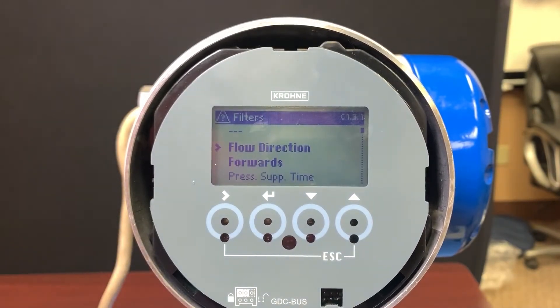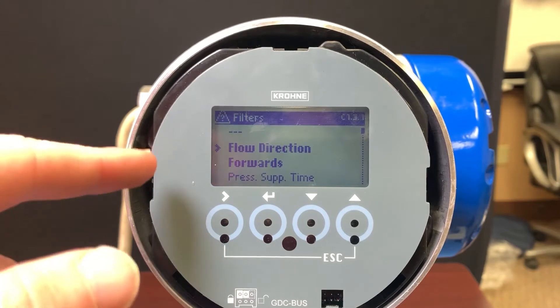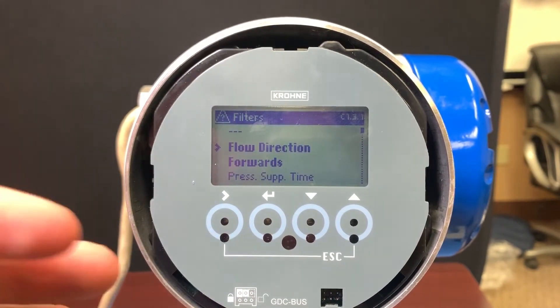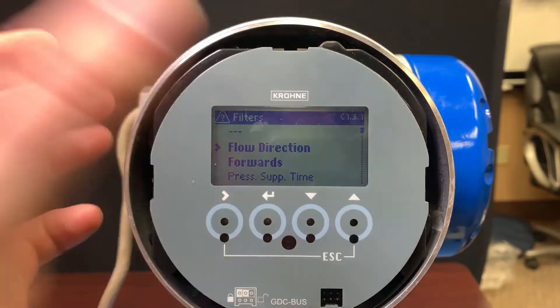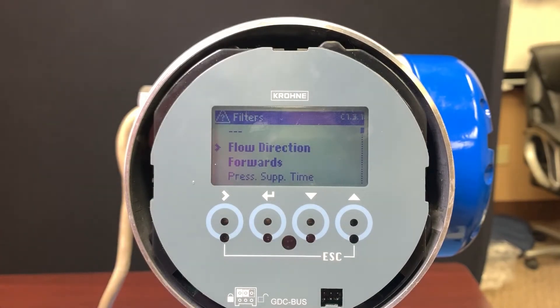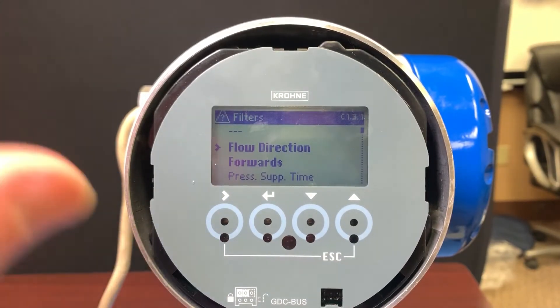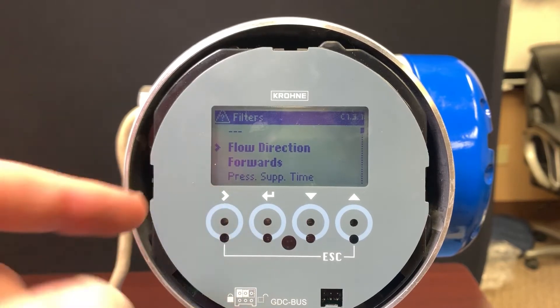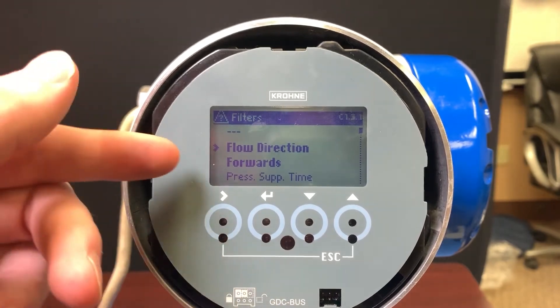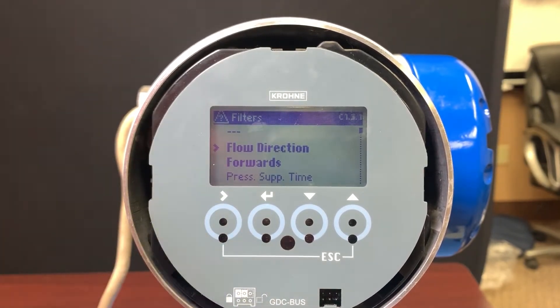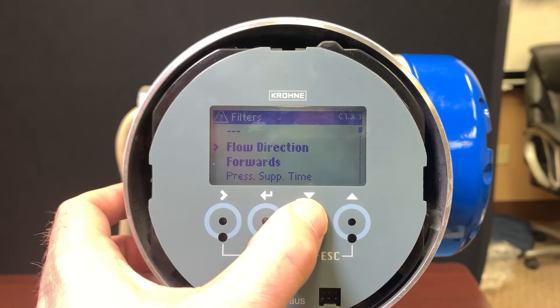The filters section is one that is used quite often. For instance, if you have a meter and the piping is running left to right but the meter was installed facing the other way, and flow is backwards based on the meter configuration, we can change the flow direction to backwards. That way we're getting the correct flow without having to physically turn the head around. The meter does give us a true indication of direction.